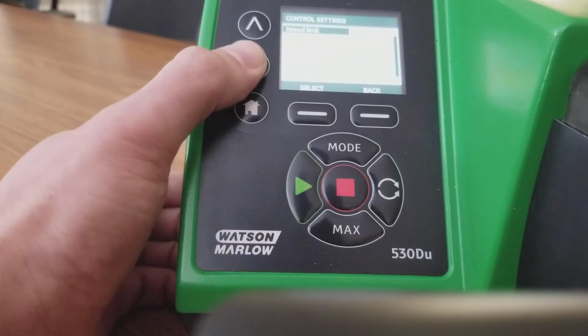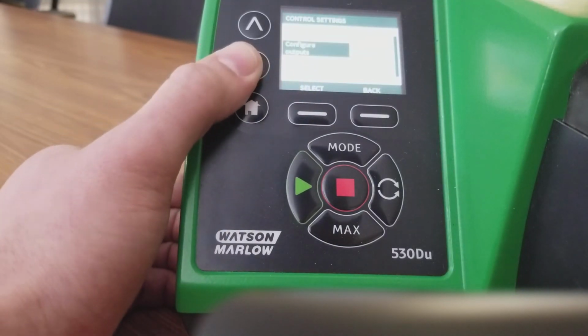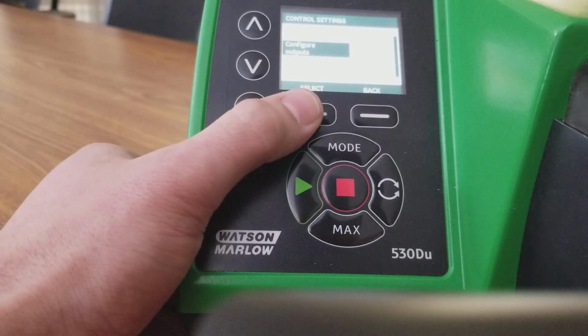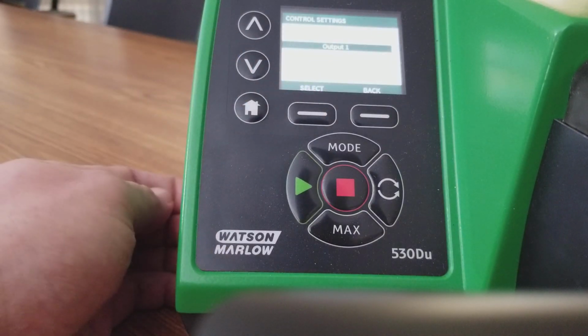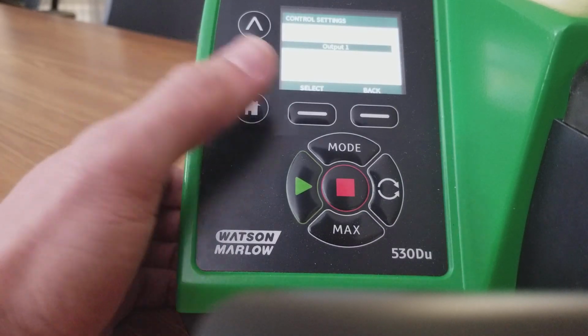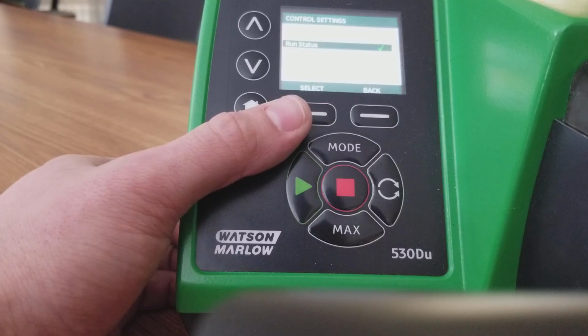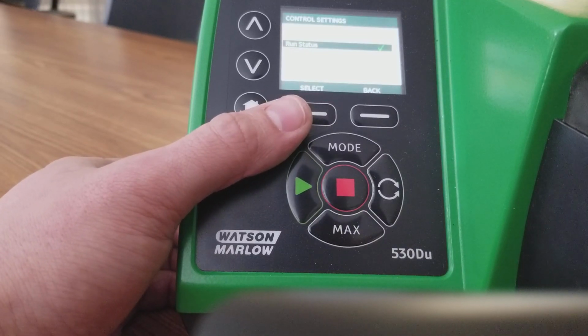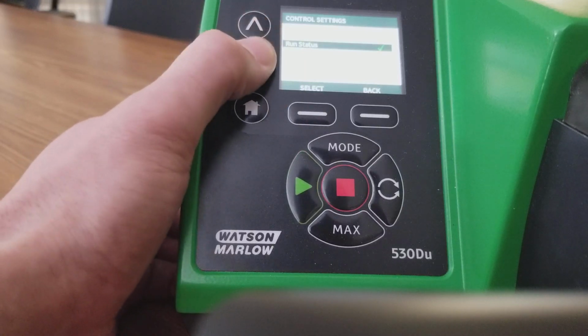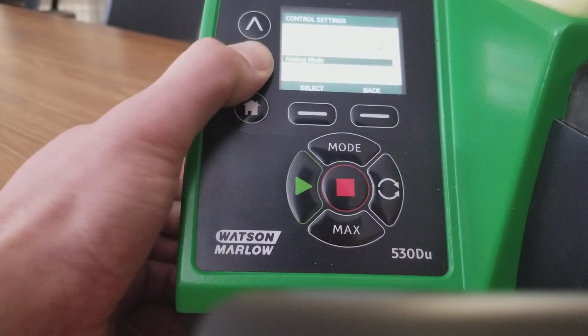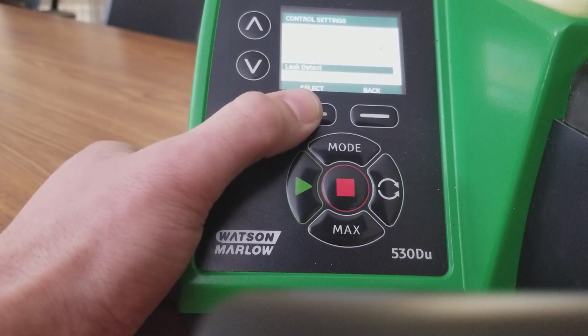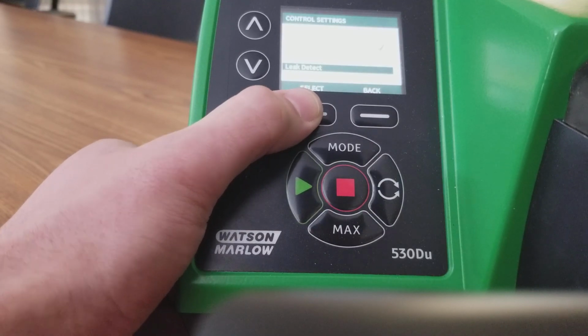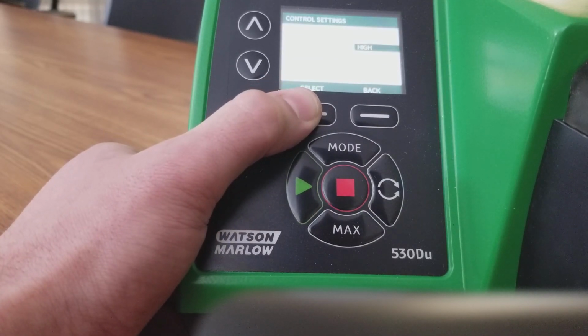In our control settings, we're mainly concerned with our configure outputs. You have 4 outputs to choose from. Those are going to be those 4 relays in the back that are wired in. And underneath there, you're going to find the options. The main one that I would suggest people use is leak detected, if they've got a leak detection attached to this. So set up on that, we hit select.